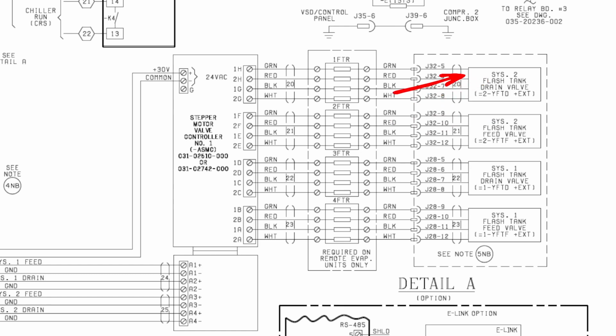Hopefully that makes sense. But those are going to be the 2 main differences you're going to see between a 4 lead or a 5 lead for these valves. The vast majority of what I see being used right now is 4 leads. Everything has moved that direction. At one point in time, it was pretty common to come across a 5 lead motor.